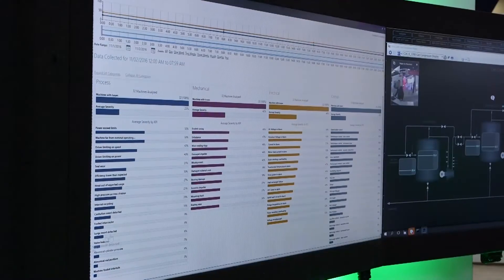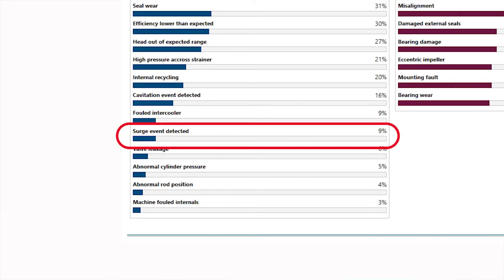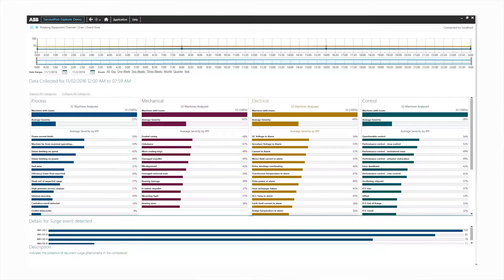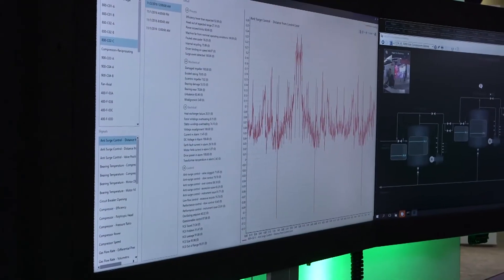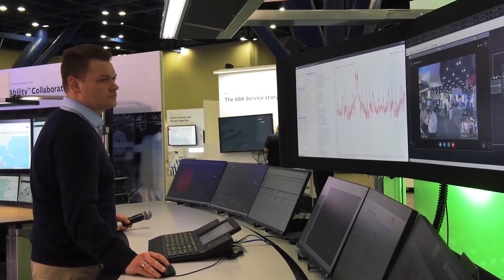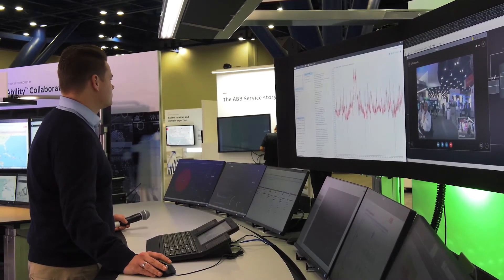There's a lot going on here. I'm suspecting this surge event — do you see that one that says surge event detected? Something about 9%. Yeah, that's usually at zero. I know there's a lot on here, but there's a profile and this should be zero. So if we click on that, it'll help us dig right into the raw data. This first one is pegged at 100, so let's click on it and see what it shows us. This allows us to sync the data with the KPI so we can exactly see what we're doing. See this surge here — this surge in the middle, it's above the noise floor. That aligns with the alarm and your dots here. So that's what you're seeing — it's not a false positive, so we don't want to be chasing rabbits. Now let's use the data analytics to navigate and find the problem.